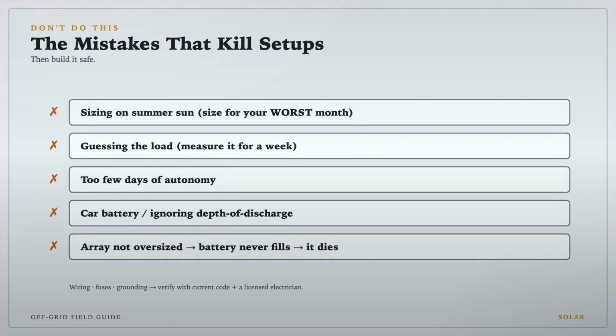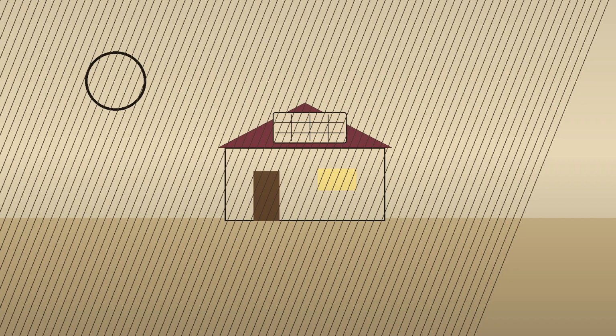Controller error codes matter. Do not clear them blindly. Overvoltage, low voltage disconnect, reverse polarity, battery temperature, and overcurrent warnings each point to a different failure. Screenshot or write down the code, then check the manual. A cheap controller with a tiny screen can still save you if you respect the message.